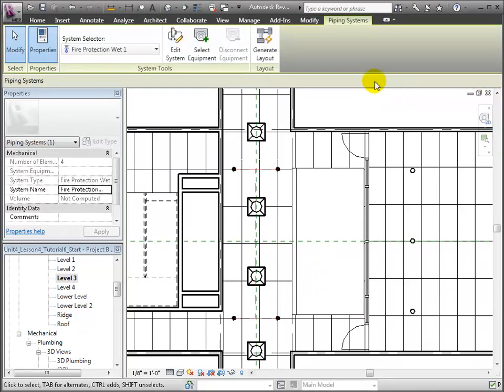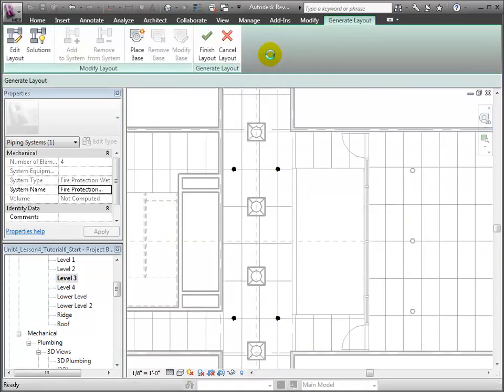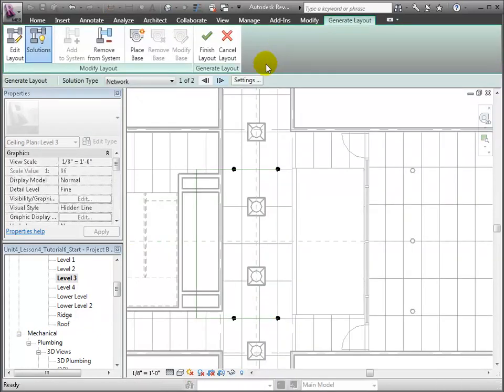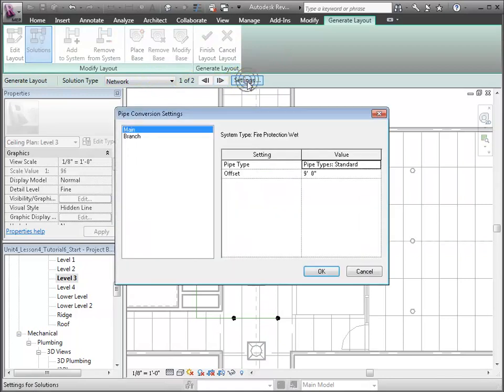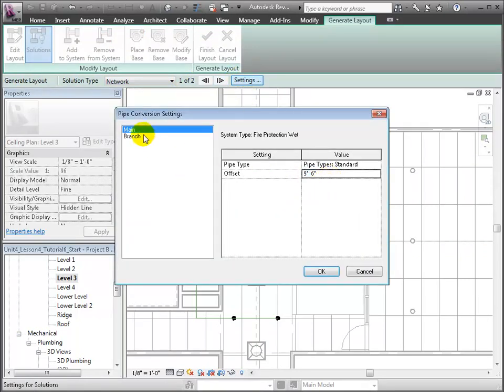The Piping Systems tab appears, and we'll choose the Generate Layout tool. Let's keep the Network option as is, but we'll enter the settings to define the offset for the main and branch pipes of this pipe network to be 9½ feet, which is just above the 9-foot ceiling.